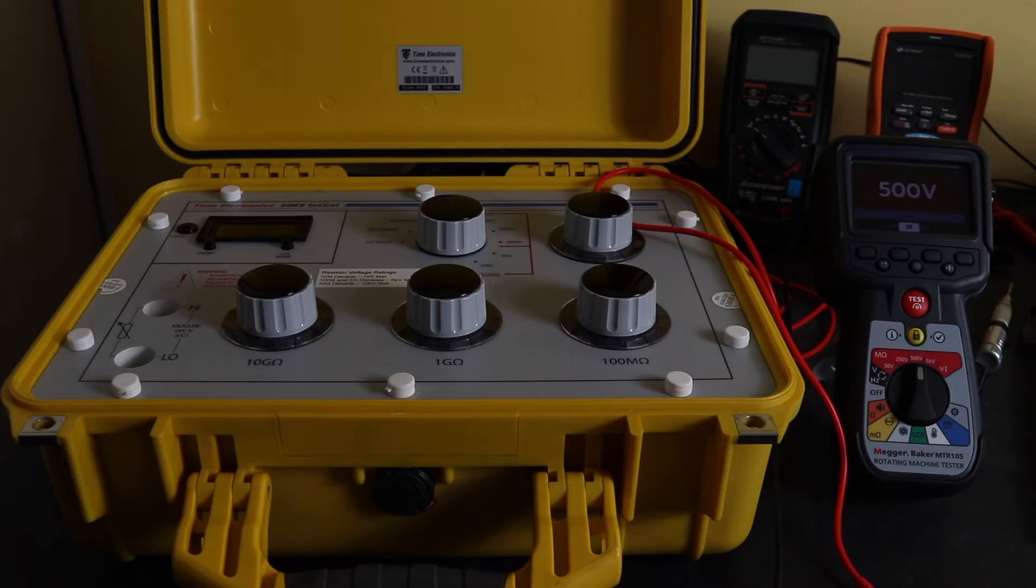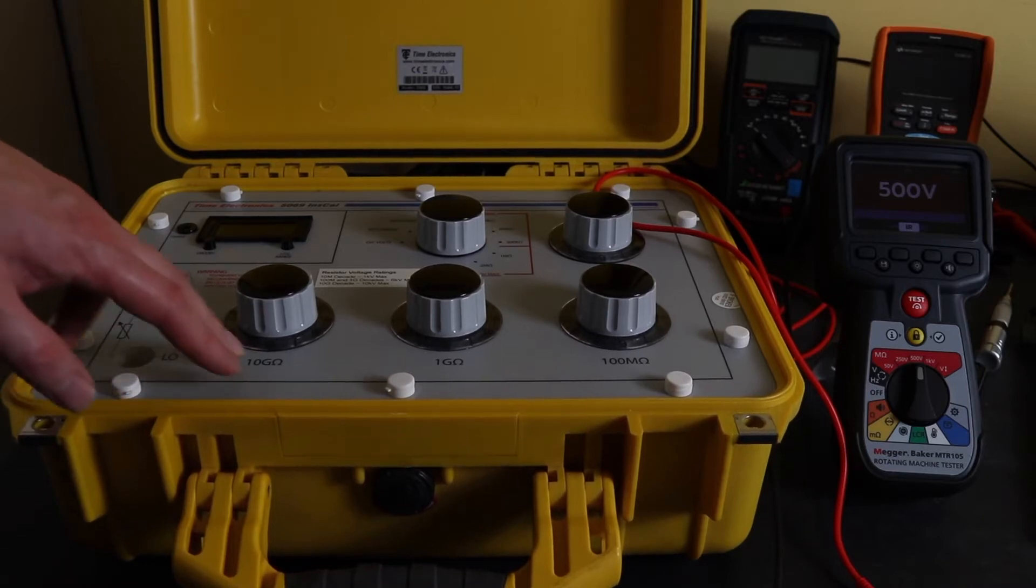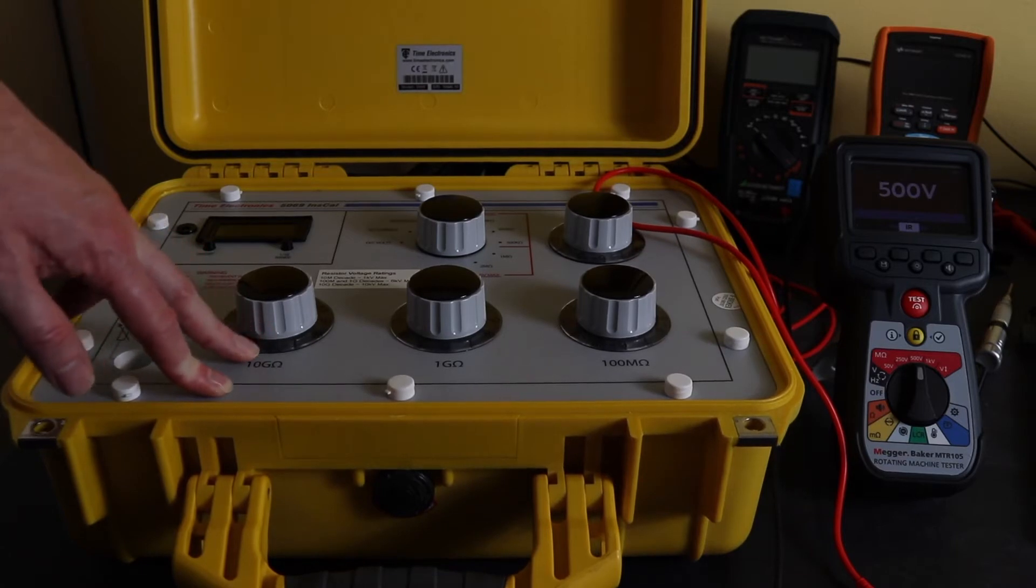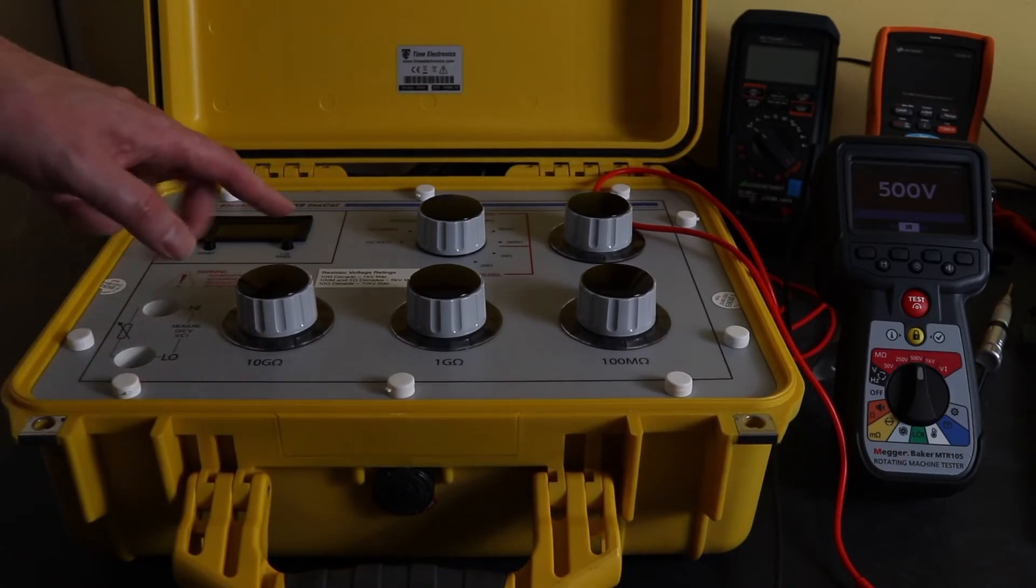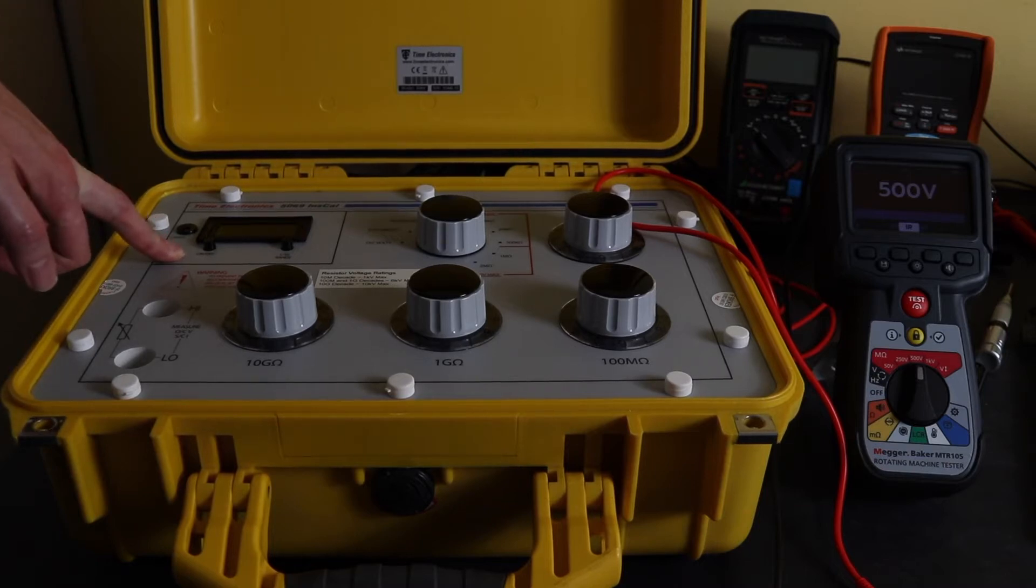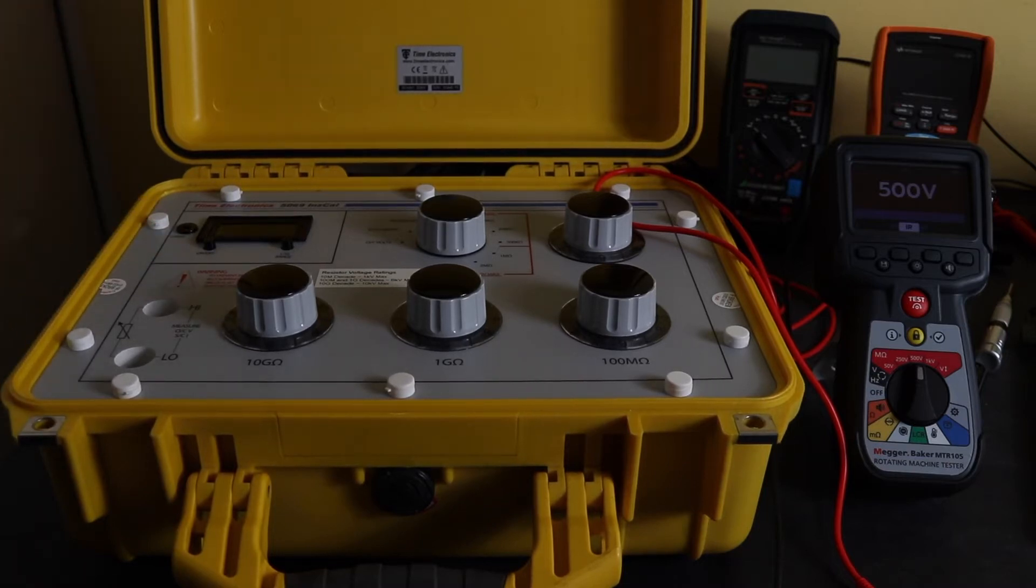To help me with that I've got the 5069 calibrator from Time Electronics. This is a set of decade resistors, high value resistors, goes up to 99 gig ohms and it also has a little meter in here so I can measure short circuit current and open circuit volts of the insulation tester.